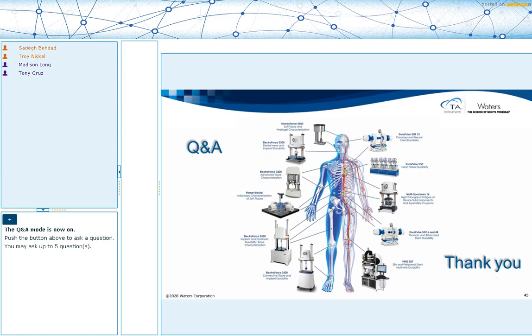Certainly in stent fatigue, with stainless steel and nitinol, there's a lot of predicate data out there in the 60 hertz range, so that tends to be the limit, but we see people pushing that higher and doing some validation. Obviously, you have to prove that out and make sure that's right when you submit to the FDA. So in general, I think the range is somewhere between 20 and 100 hertz, and you have to assess whether your material is significantly dependent on that frequency, and if so, do a good study and prove to the FDA that the test that you do is relevant and applicable.